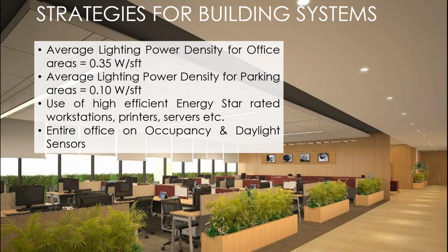There is a term which we use, I'm sure you must have all read in the ECBC. It's called luminous efficacy, which is lumens per watt. That is the output of a light fixture in lumens divided by the input power consumption, which is wattage. And the fixtures which we are using here are 165 lumens per watt, whereas what the regular brands give in India like Philips and Wipro and Bajaj, maybe 120, 130, maybe going up to 140. But this is the product which we are using, 165 plus lumens per watt, and we have been able to get this. Similarly, for car parking areas, it is 0.1 watt per square feet.